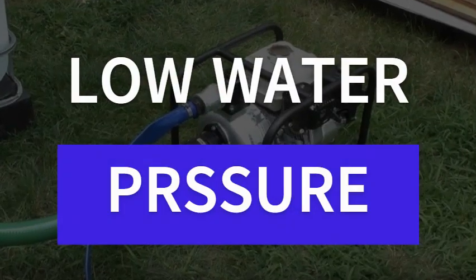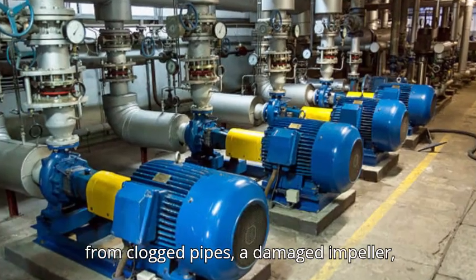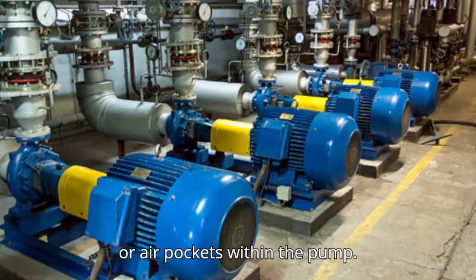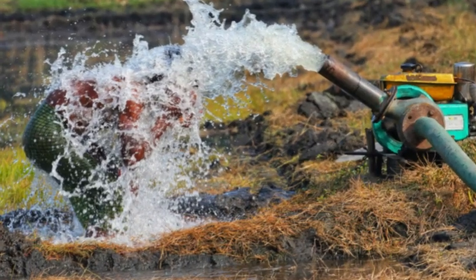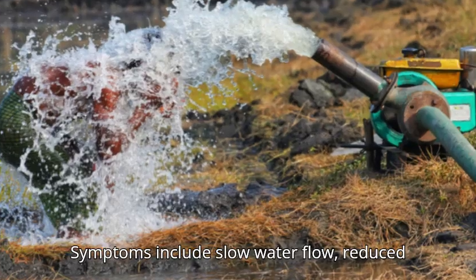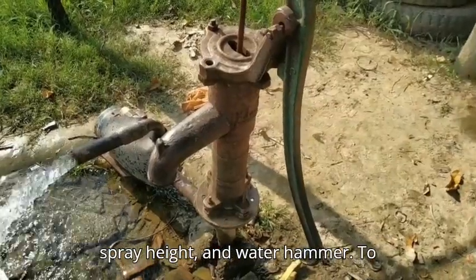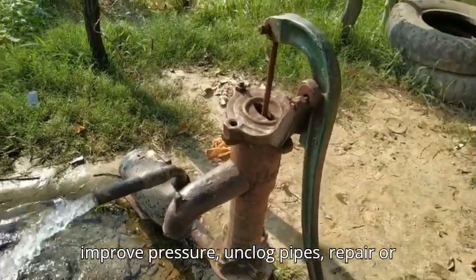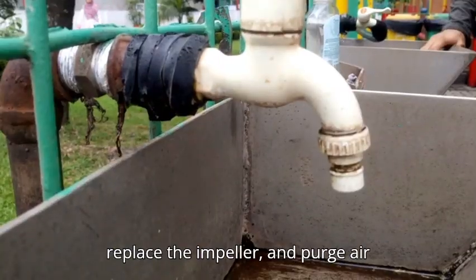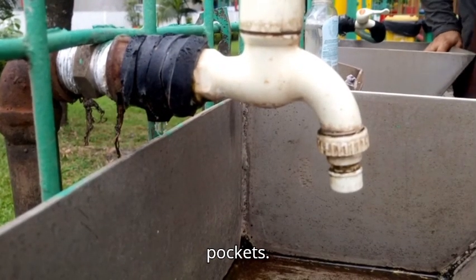Low water pressure. This can result from clogged pipes, a damaged impeller, or air pockets within the pump. Symptoms include slow water flow, reduced spray height, and water hammer. To improve pressure, unclog pipes, repair or replace the impeller, and purge air pockets.